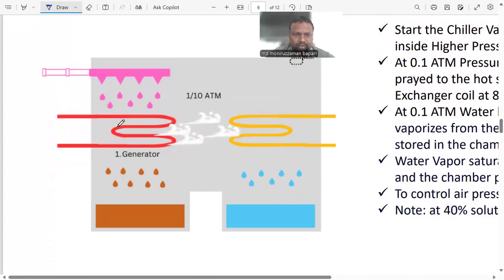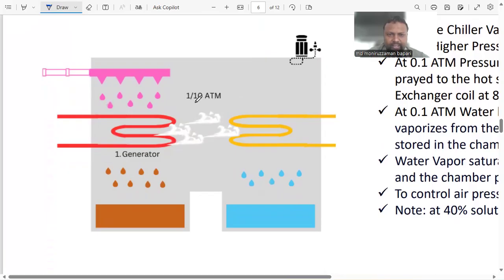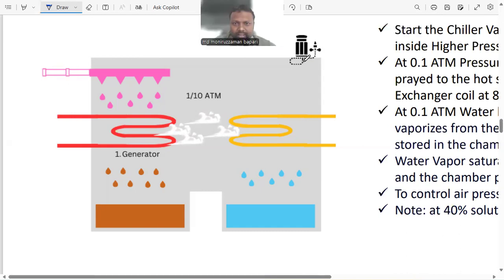Okay. Now let's talk about generator first. This is the higher pressure chamber. In higher pressure chamber, the pressure is 1/10 of atmospheric pressure. And there is a vacuum pump here. So whenever, let's say the very morning you come in the plant and you start the chiller, firstly the vacuum pump is going to make vacuum and will create a low pressure inside as low as 1/10 of atmospheric pressure. After it is done, vacuum pump will be stopped and the cycle will start.